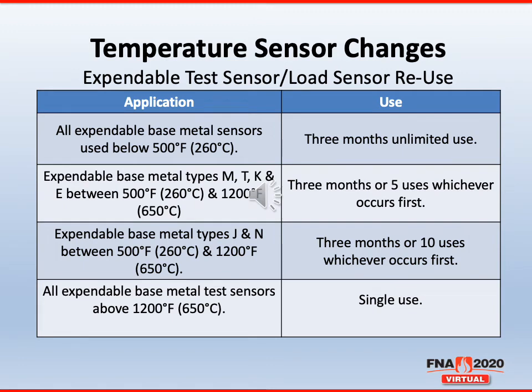One of the major changes that occurred in AMS 2750 when it came to thermocouples was those that are being used for test sensors or load sensors and their expendable type thermocouples. The changes that we made were based on studies that the AMS 2750F subteam conducted during the draft portion of the specification, where we saw some considerable drift when it came to expendable base metal thermocouples. So we made some restrictions in regards to expendable base metal thermocouples, and they are as follows.